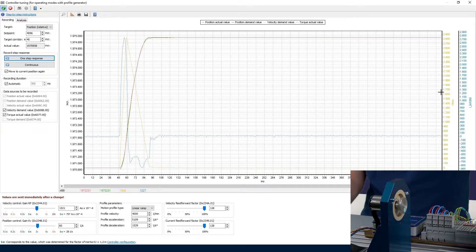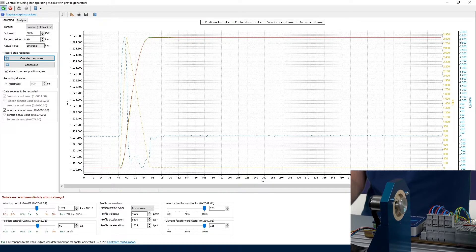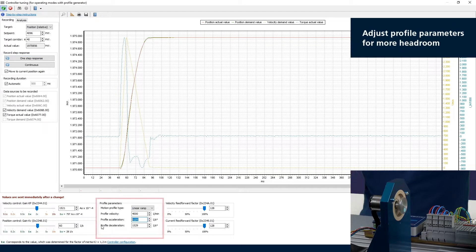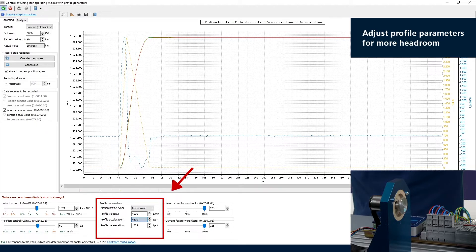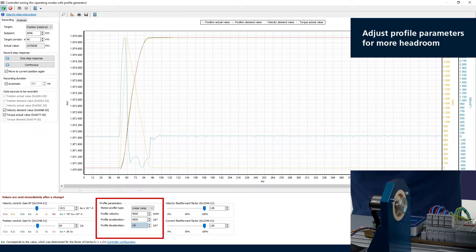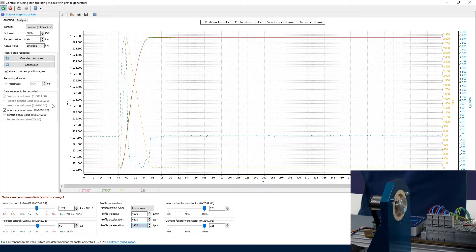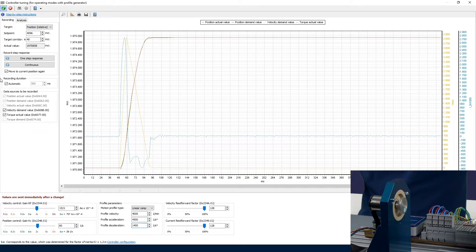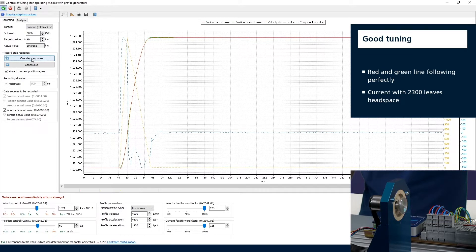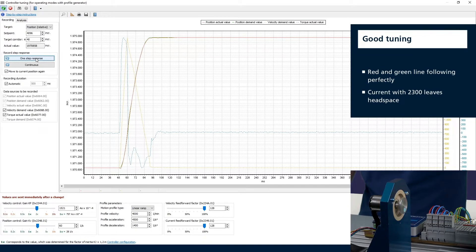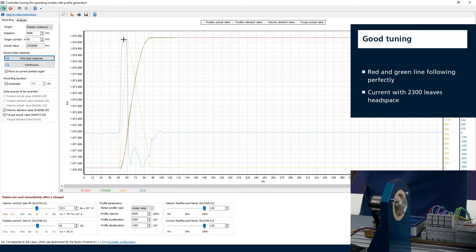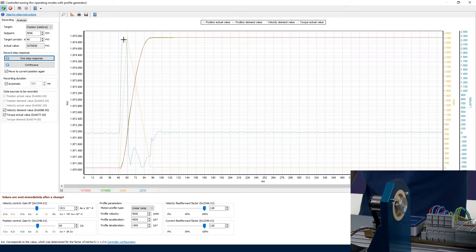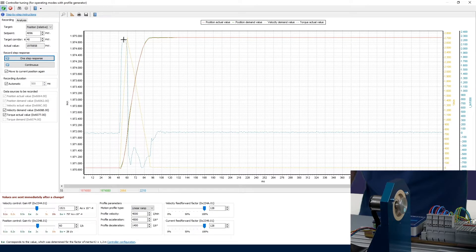For a servo drive like here, we preset a maximum of 3000, so a maximum of three times the nominal current can be used for acceleration, deceleration. We reach about 2800, which is very close to the maximum. So the suggestion here is to reduce the profile parameters a little bit in order to have more headroom for dealing with disturbances, which we are going to see in one of the next videos, of course. So these are changed, one more step here. Following perfectly, but now the peak here is in the range of 2300, so enough headroom to compensate whatever deviation or disturbing torque you might have.